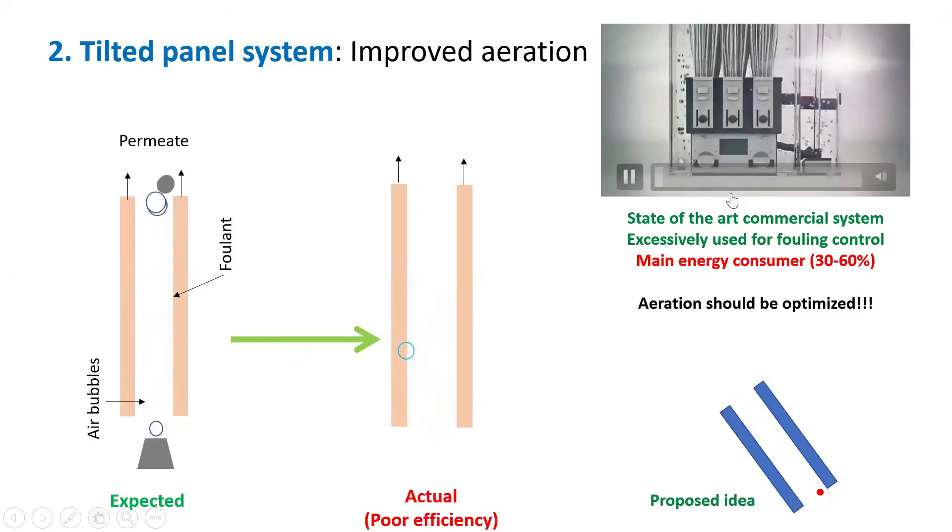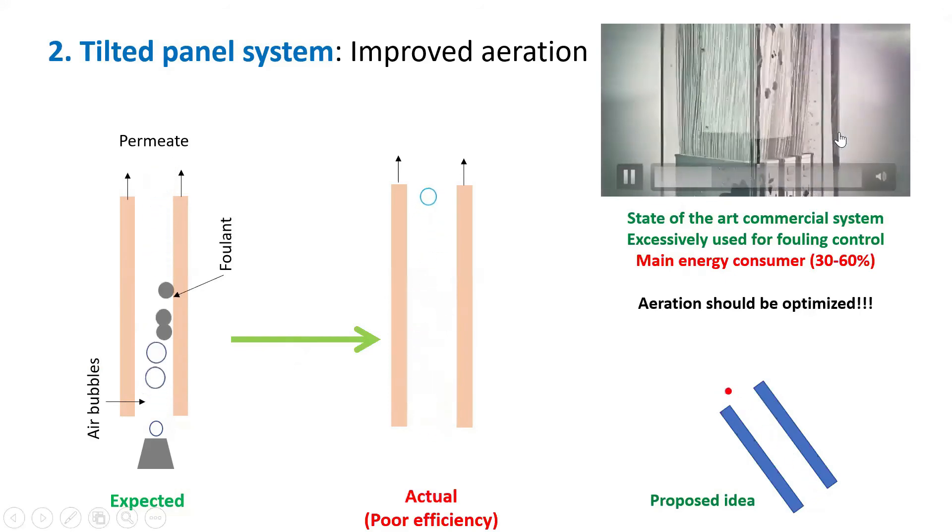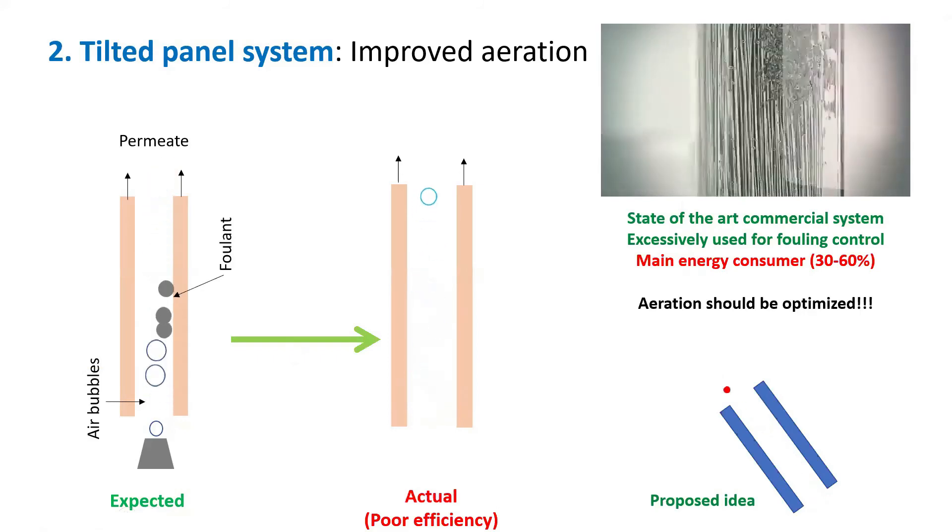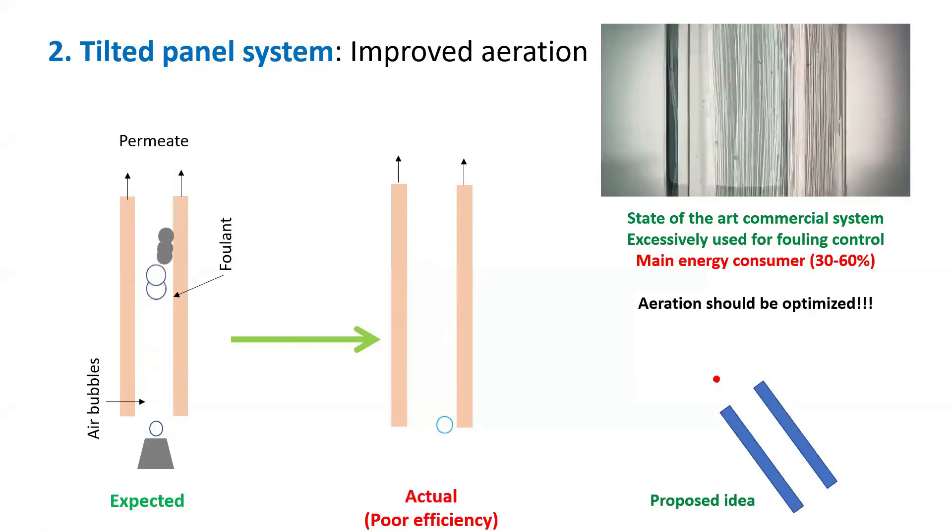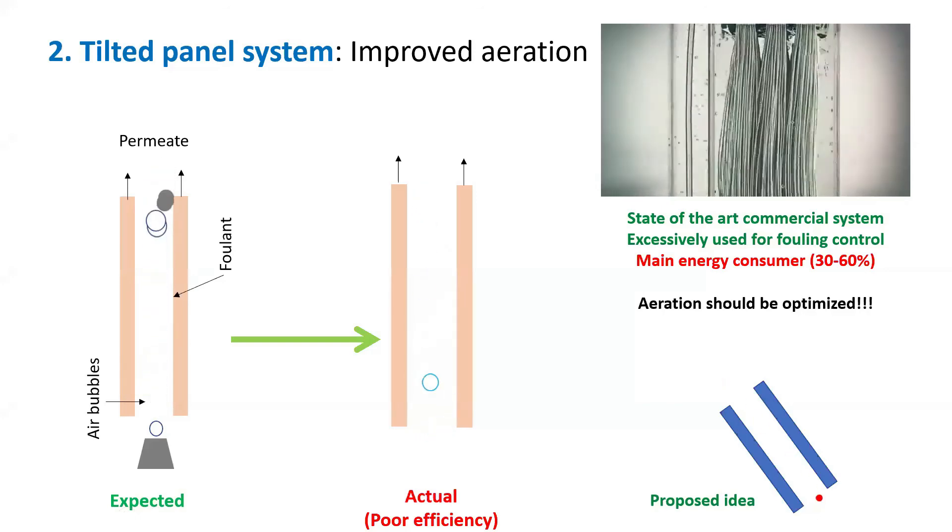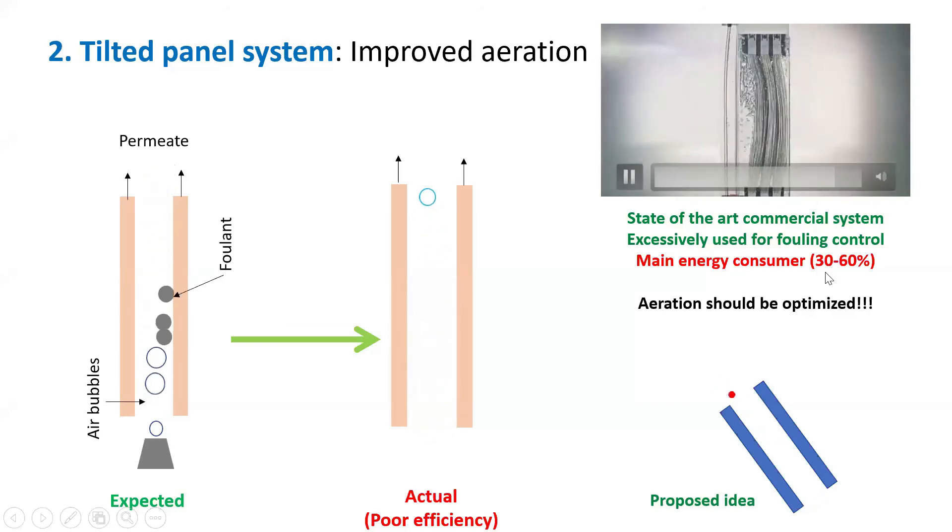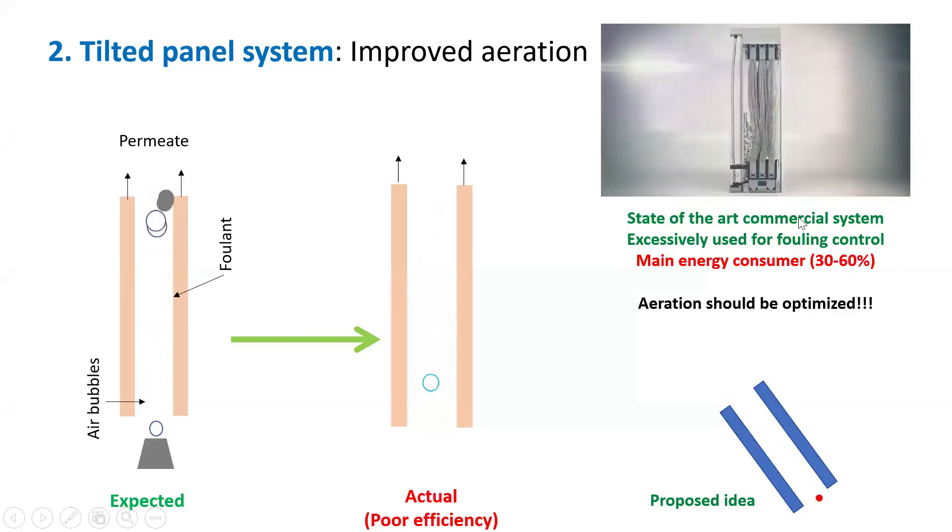The state-of-the-art way of aeration, you can see here, this is called a GE MBR. As you can see, they pump a lot of air, and then for the hollow fiber module, it allows them to sway into swings, and then you can achieve the enhanced cleaning. But the consequences is that if you apply a large amount of air to clean off the membranes, you have high energy consumption. Mainly for coarse bubble aeration, it can go up to 60% of the energy input.